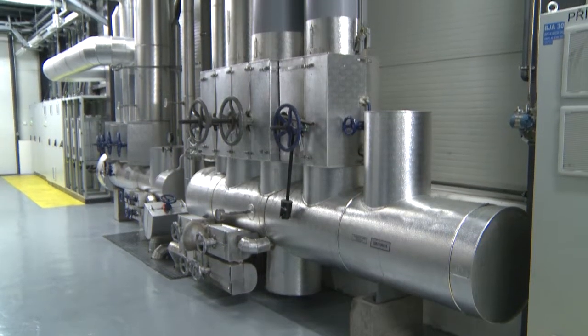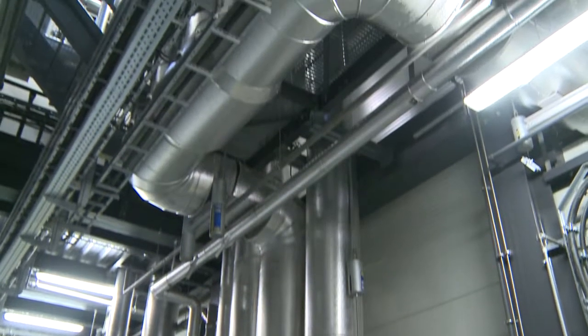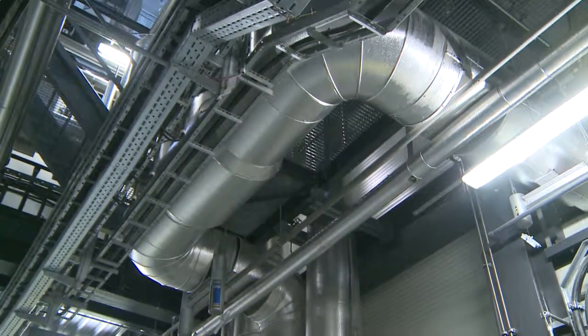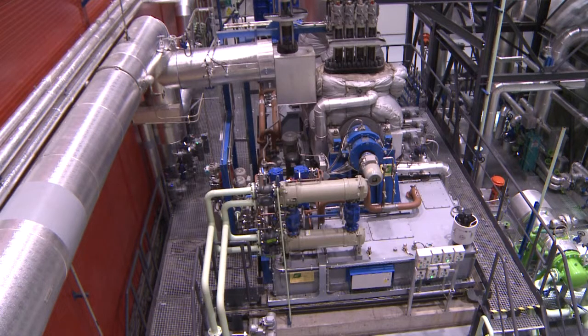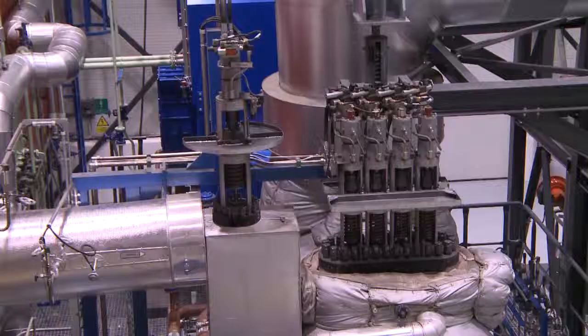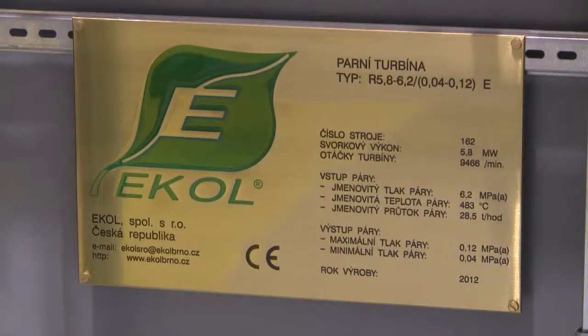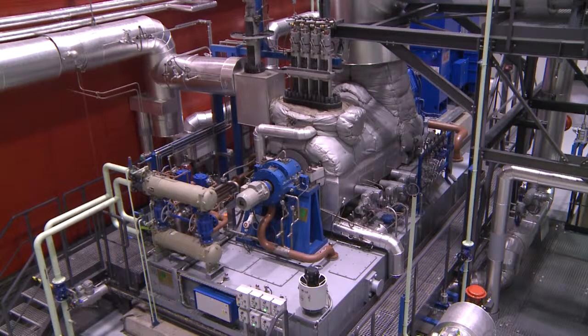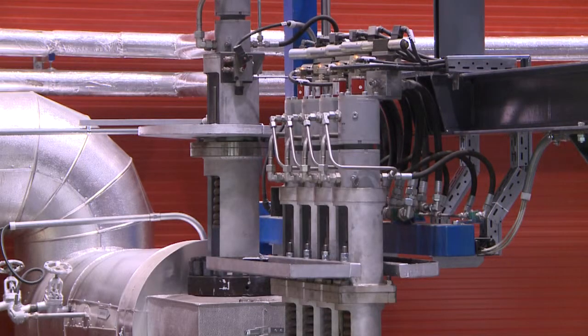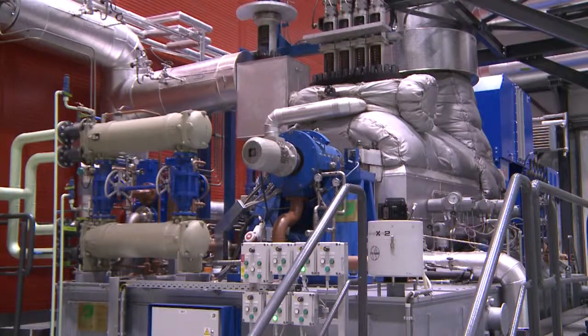The steam from the boiler to the turbine is taken from the boiler house to the turbine hall through a partition. In the turbine hall, the steam is taken through the regulating valves of the precisely controlled EKOL steam back-pressure turbine with an output of 5.8 megawatts at 9,466 revolutions per minute. The estimated annual amount of electricity production is 36 gigawatt hours.